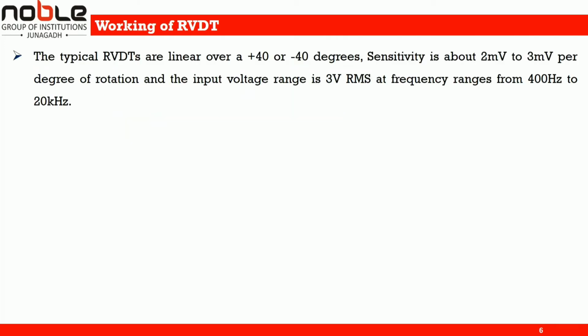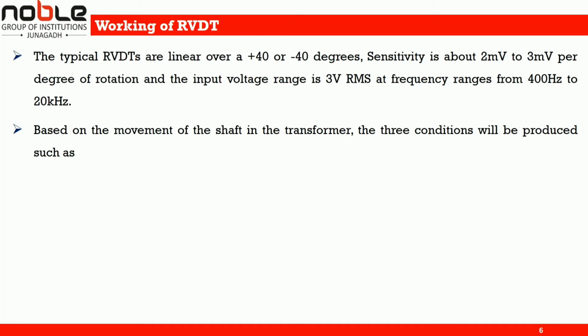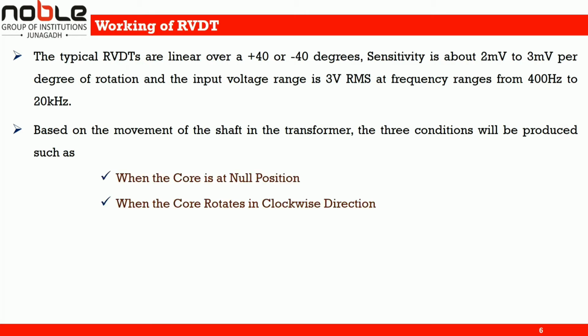The typical RVDTs are linear over plus or minus 40 degrees. Sensitivity is about 2 millivolt to 3 millivolt per degree of rotation, and the input voltage is 3 volt RMS at a frequency ranging from 400 Hz to 20 kHz. Based on the movement of the shaft in the transformer, three conditions will be produced: when the core is at null position, when the core rotates in clockwise direction, and when the core rotates in anti-clockwise direction.